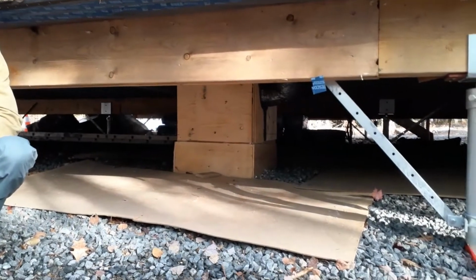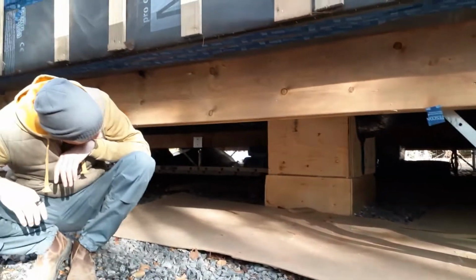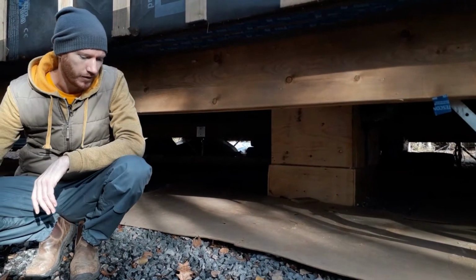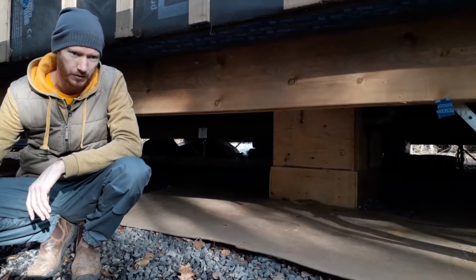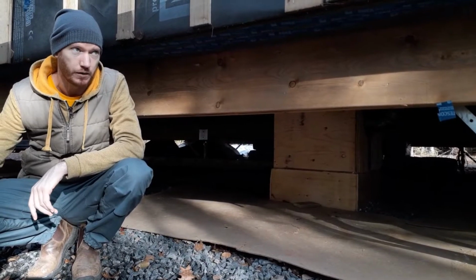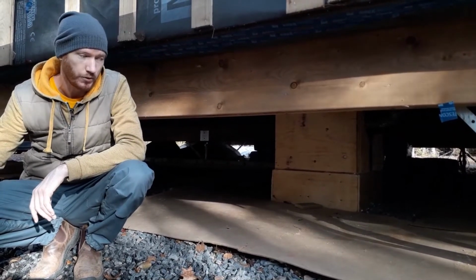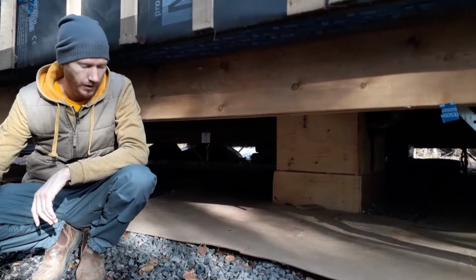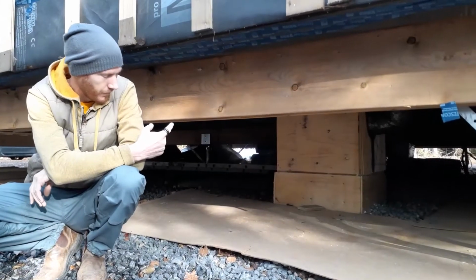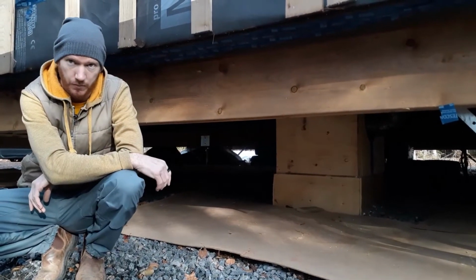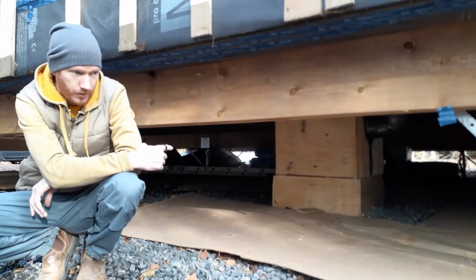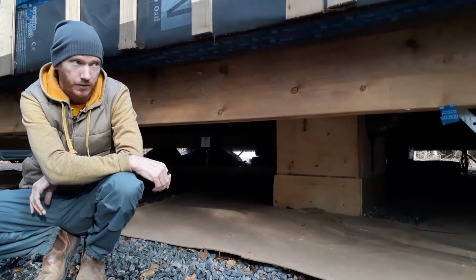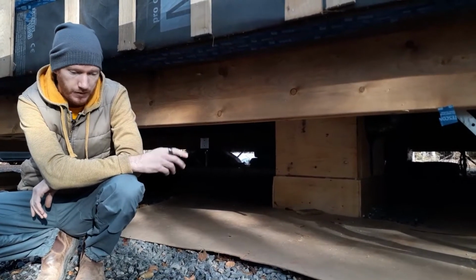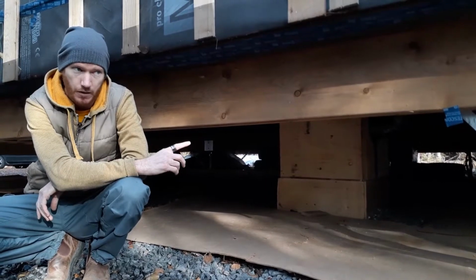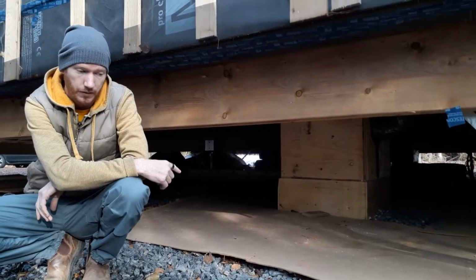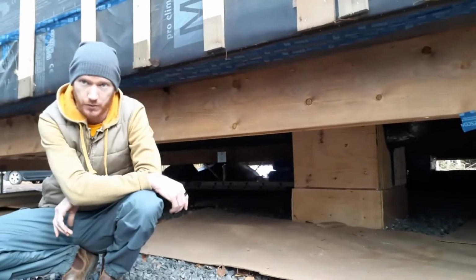The big box behind me is one of our service cavities for the site services coming into or exiting the building. The lot is on municipal water and sewer, and we've got hydro at the road. So there's an electrical service, sewer and water supply pipes inside this conduit, plus two other entrance points to this 2-unit building. The conduit is insulated, and there's also a heat trace line on the supply water inside the conduit, just to protect from any potential freeze damage.